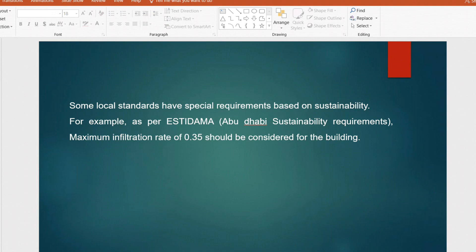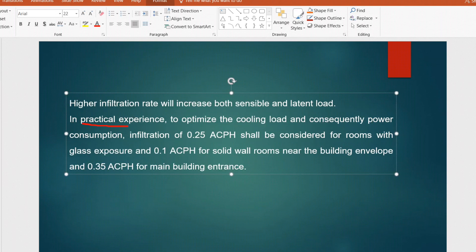Additionally, most local standards — for example the Abu Dhabi sustainability requirement from ESTIDAMA — recommend a maximum infiltration rate of 0.35 air changes per hour for buildings. Based on the application you can follow CIBSE or your local code. From practical experience, to optimize cooling load and power consumption: 0.25 air changes per hour for rooms with glass exposure, 0.1 air changes per hour for solid wall rooms near the building envelope, and 0.35 air changes per hour for main building entrances.